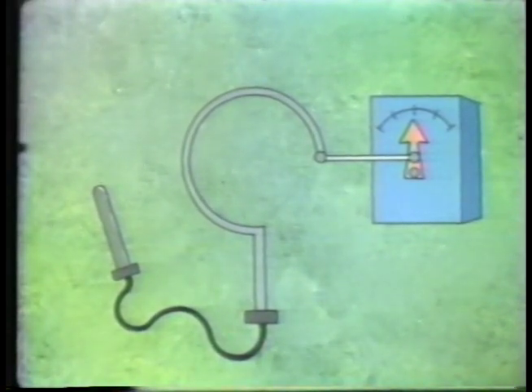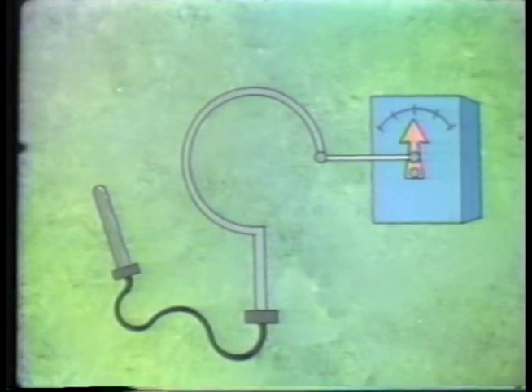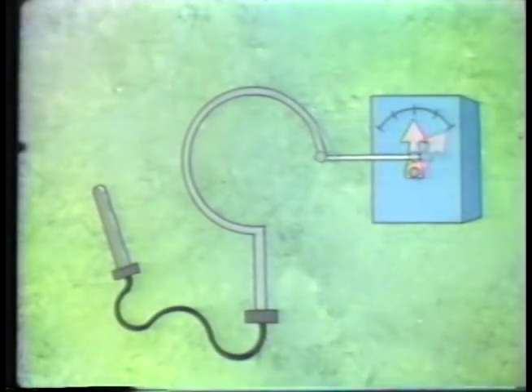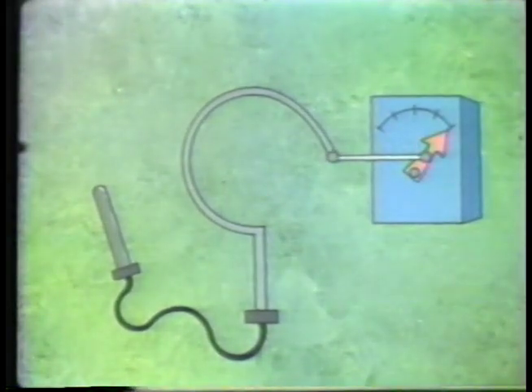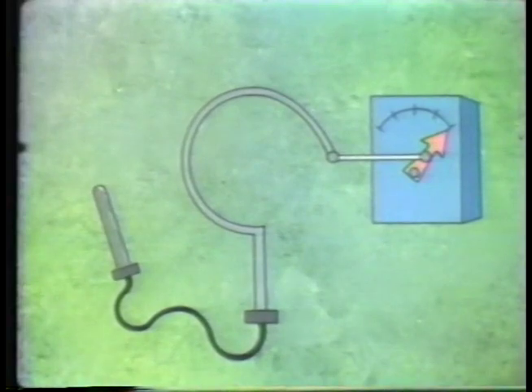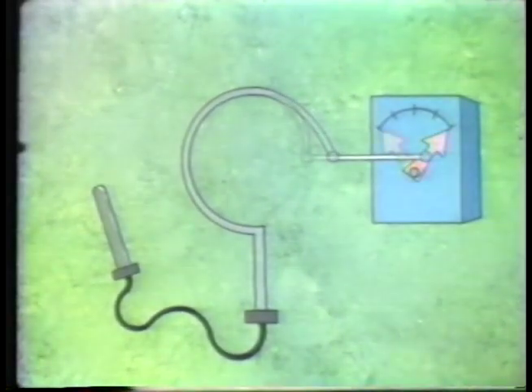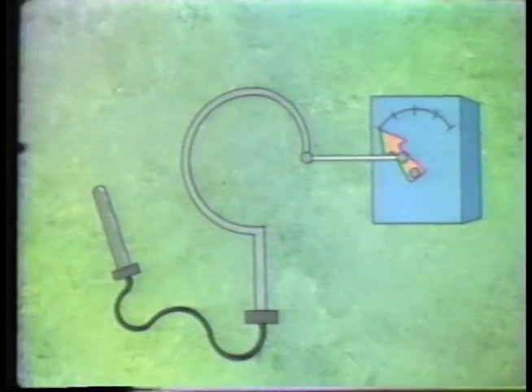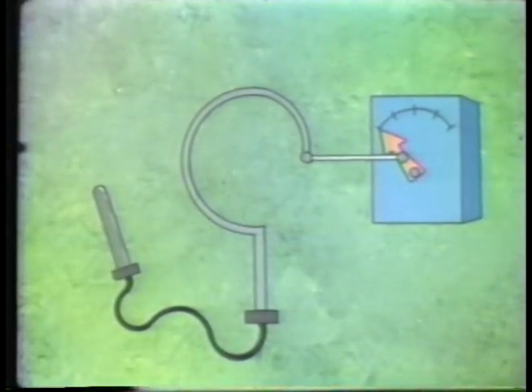When the temperature increases, the fluid in the system expands, increasing the pressure. The Bourdon tube reacts to this pressure increase and mechanical linkage moves the pointer along the scale to indicate the temperature. If temperature decreases, the fluid contracts and the fluid pressure decreases. Again, the Bourdon tube reacts to this decrease in pressure and repositions the pointer accordingly.